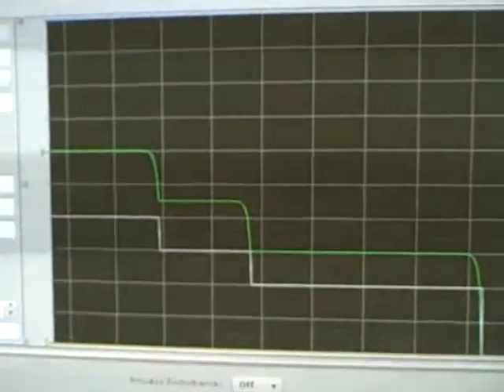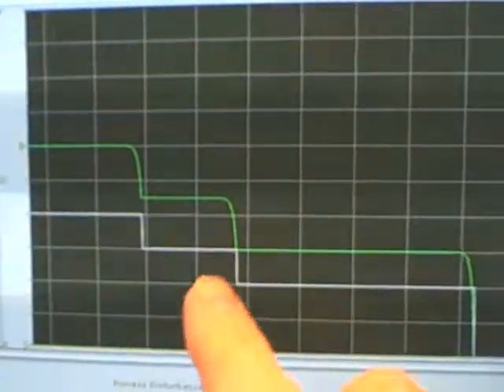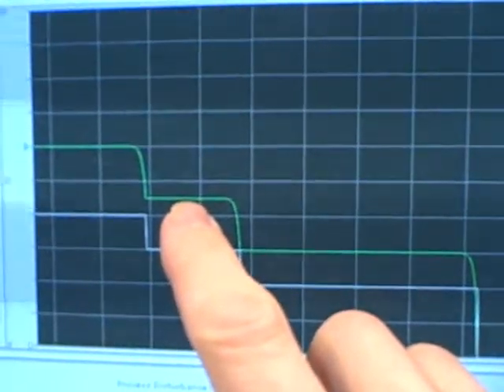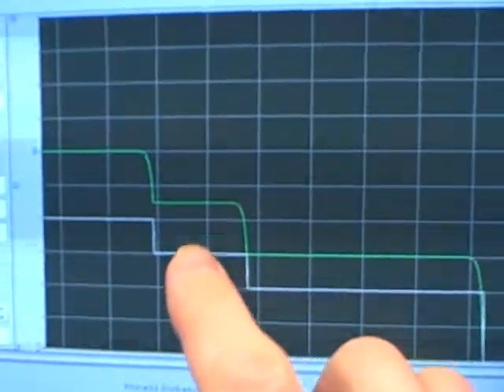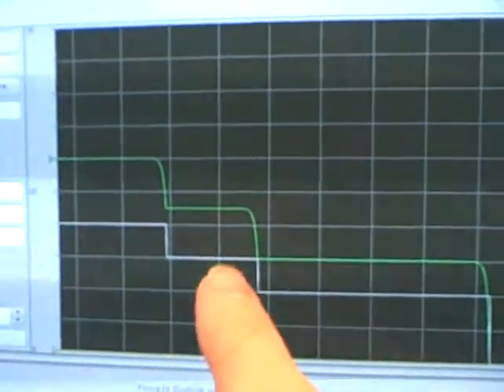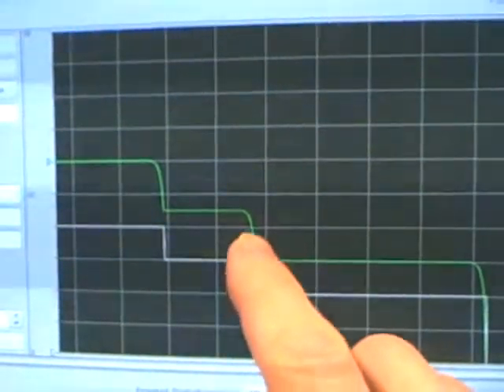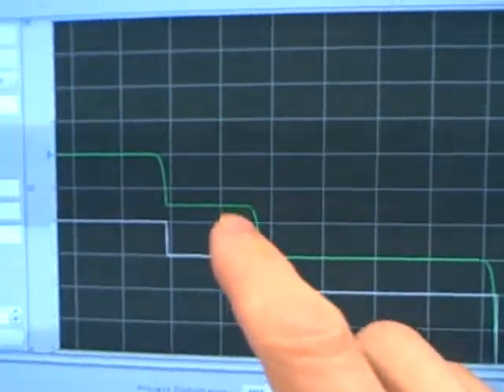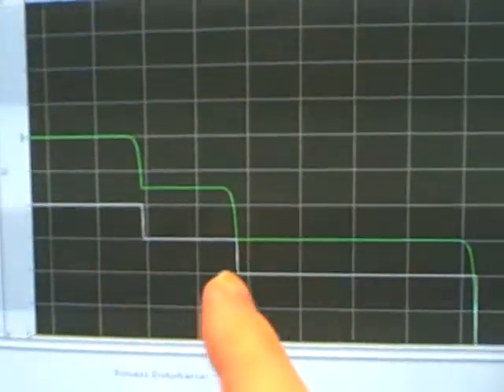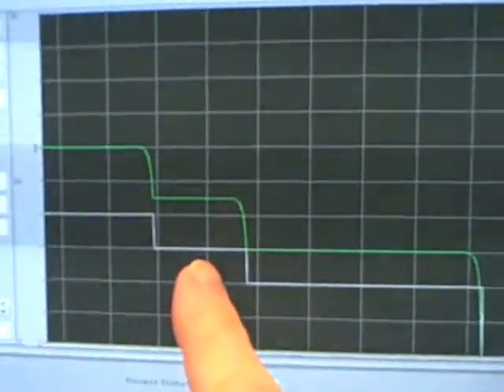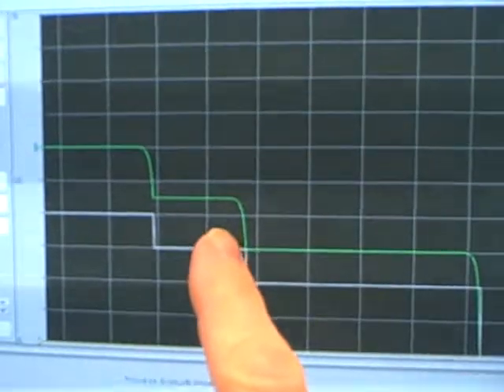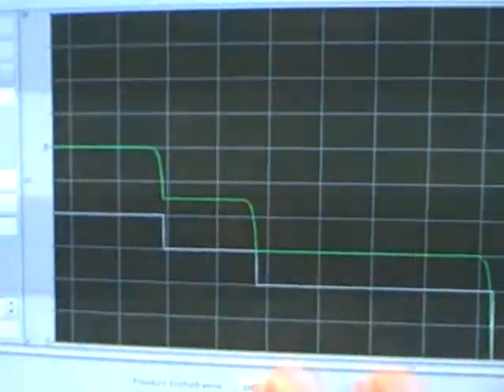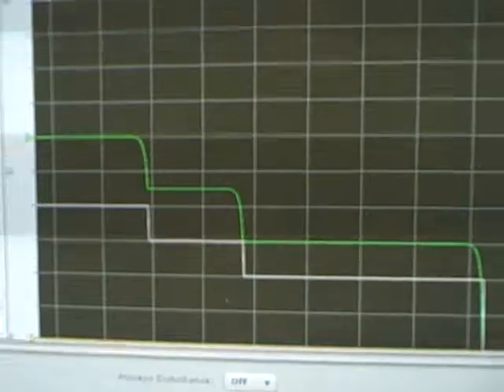The process is self-regulating in that it's able to achieve a new point of equilibrium without any help from the controller. The controller here is in manual mode, not in automatic, so the fact the process variable leveled out is not due to any corrective action on the controller's part. All we did with the controller is simply gave it a manual mode step change, and we're letting the process naturally behave as it would on its own with no automatic control action whatsoever.